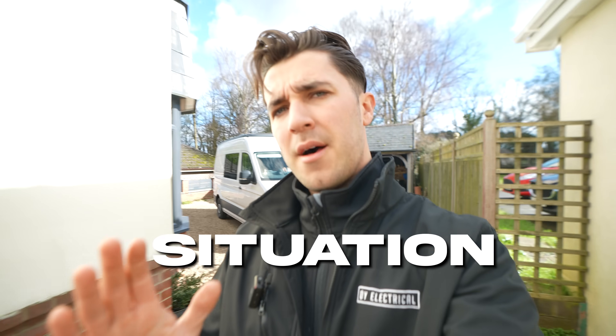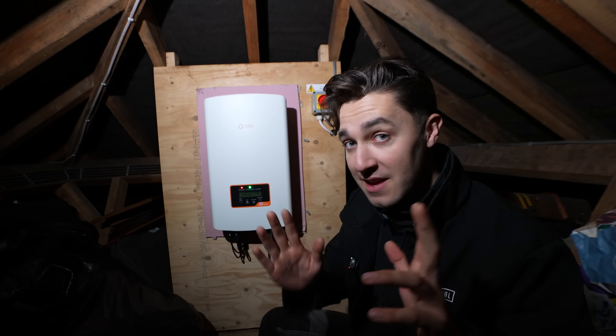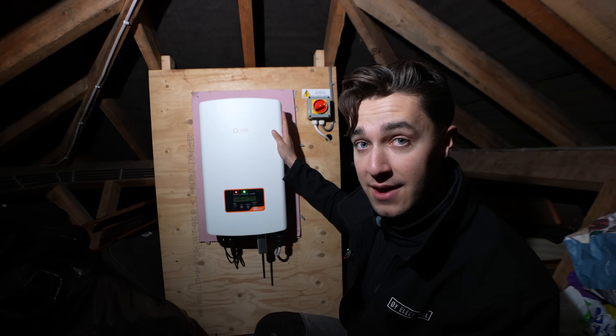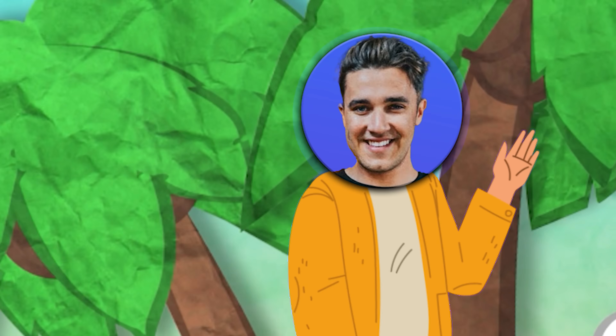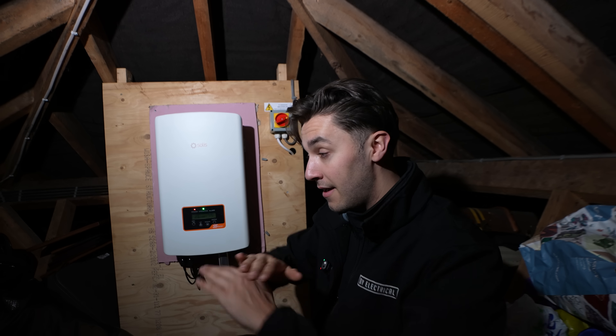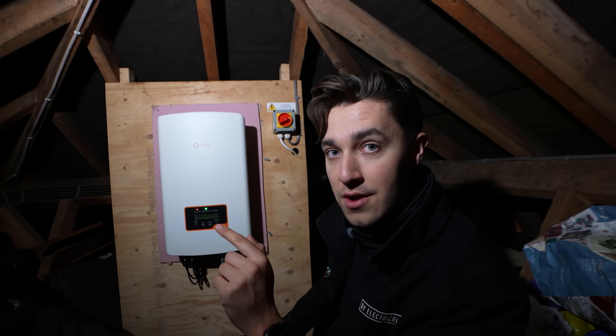Situation: we have a power cut but we've got solar installed, it's a lovely sunny day, should be absolutely fine, right? Wrong. Because sadly most inverters are like this one here, which is a normal ENA G98 and G99 compliant inverter. That stipulates within those documents that all inverters have to have an anti-islanding mode. If there is any instability in the grid, any power cuts, power fluctuations in voltages, this thing has to switch off. So actually your solar will not work in an off-grid scenario.